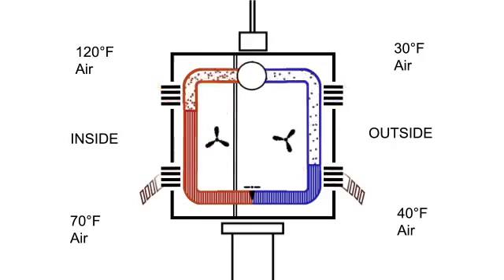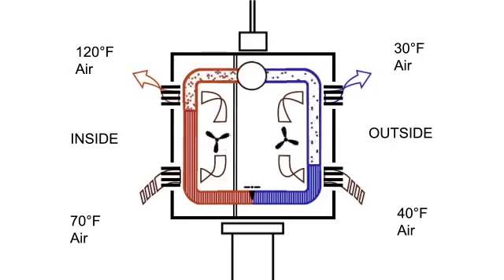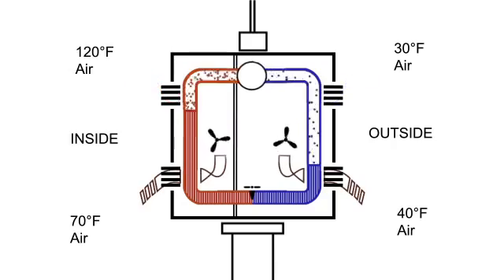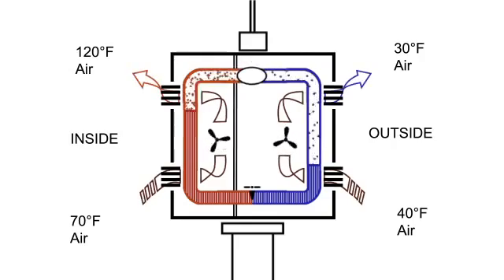Note that in the wintertime condition, the heating mode, we are asking the coolant to evaporate in cold air. But when the air is very cold, fluid doesn't want to evaporate, and the compressor must work especially hard to create the appropriate pressure to force evaporation.